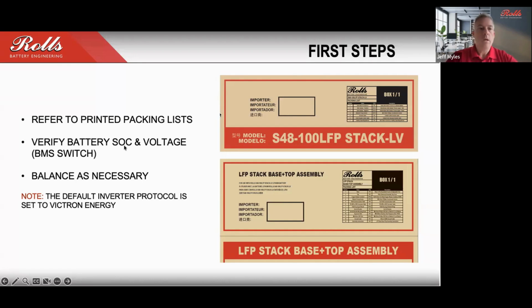One thing that I will mention, and this actually came up with a customer yesterday, is that the unit will come pre-loaded by default to work with Victron Energy inverters. The reason for that is that during the development process, that's what we were using for testing purposes, and we have to assign one inverter protocol to the unit. So out of the box, it will work directly with Victron Energy components. If you're going to be connecting it with a different inverter, then you'll go through the inverter protocol setup process to assign the corresponding protocol.